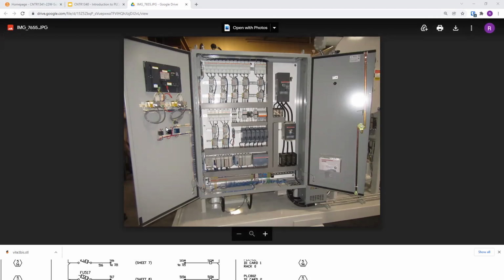We've got a couple of relays at the top. All of our systems have a phase relay as well. If they have 3-phase power come in backwards or they lose a phase, it will send a signal to the PLC that will stop the system. So if they blow a fuse or something, it kills the whole system so that they don't single-phase a motor or overrun a heater.